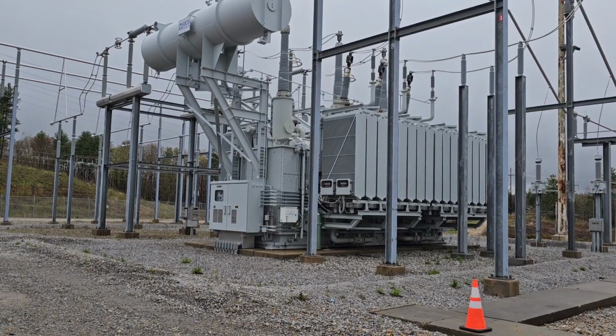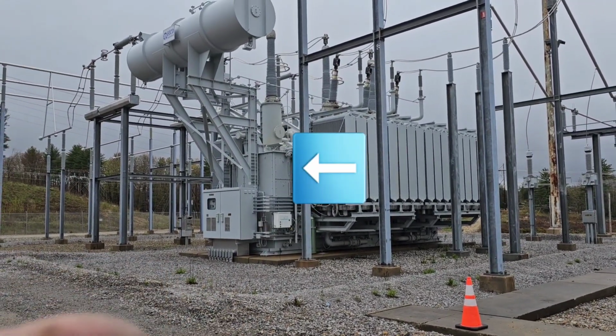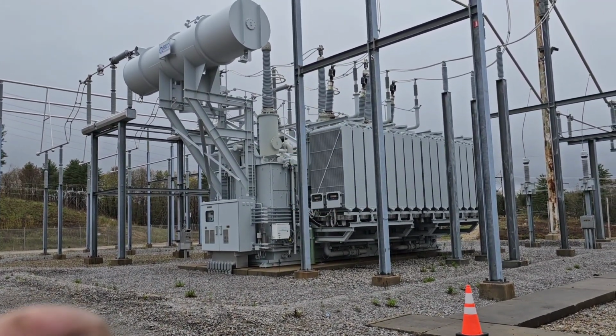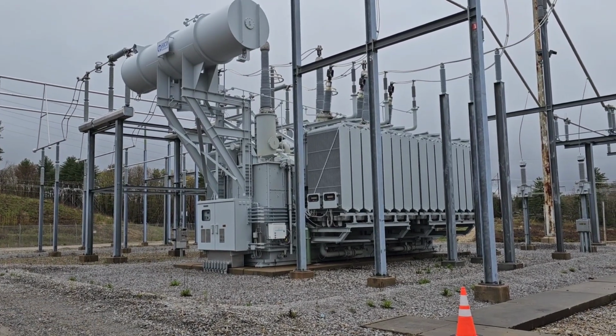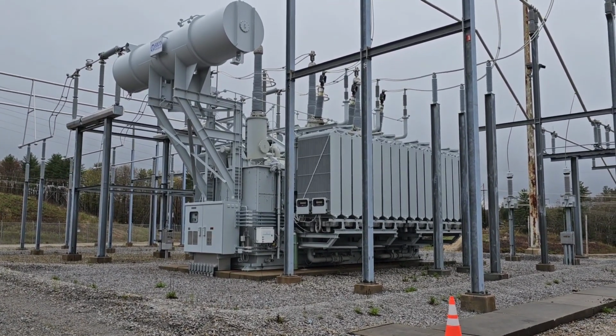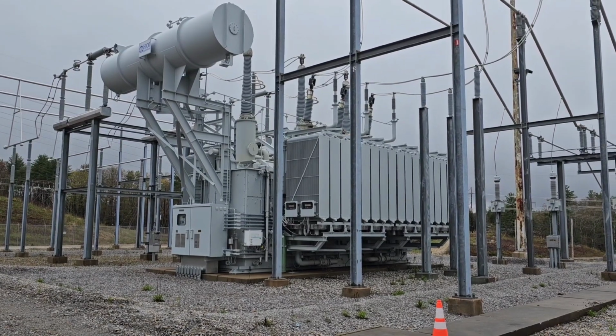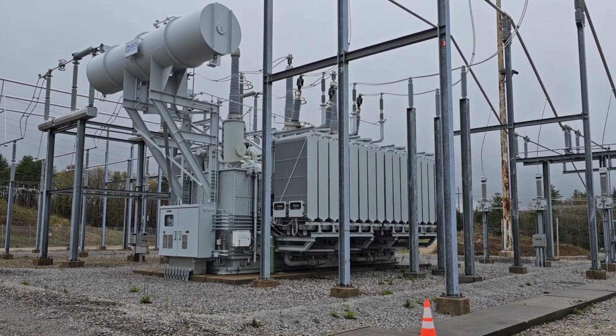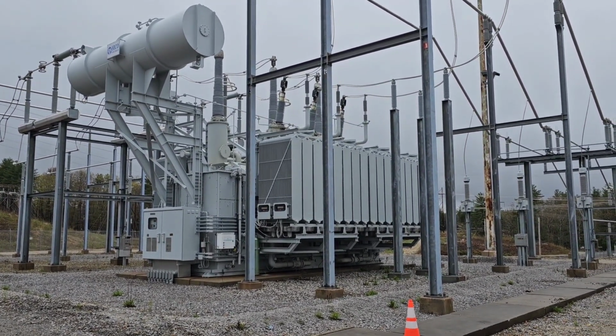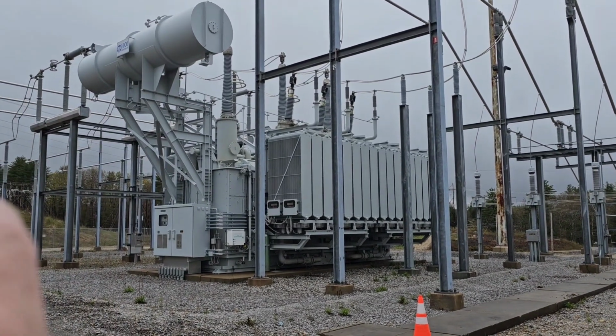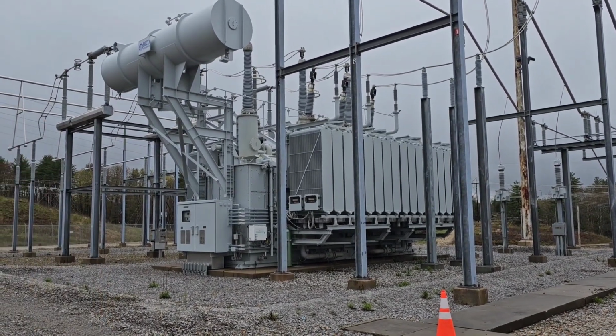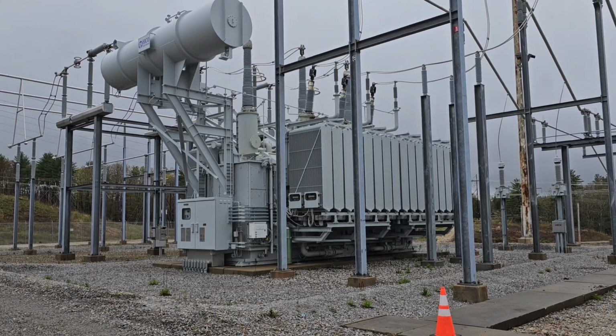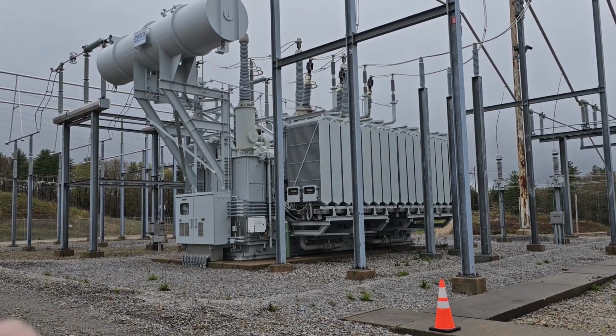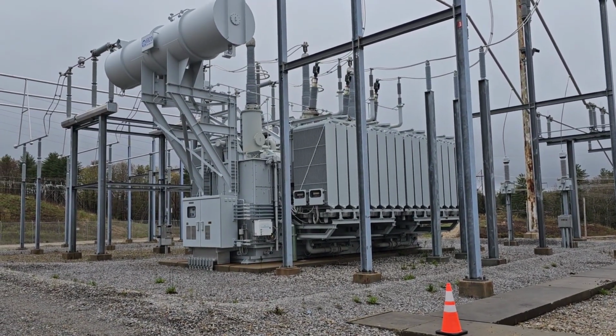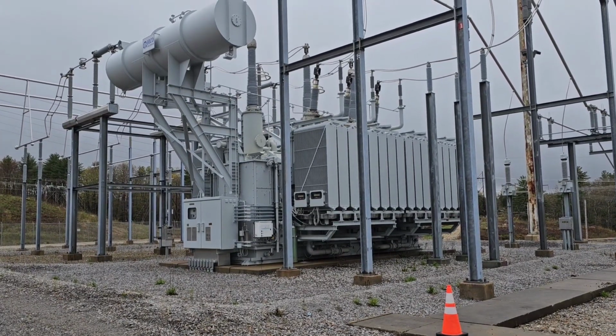This has what's called a load tap changer on it, so it can change the ratio slightly to adjust for power demand. We can get more into that later, but that's basically what this is and how it works. So if 100,000 volts goes in on the low side, 300,000 volts comes out on the high side. And if 300 amps goes in on the low side, 100 amps goes out on the high side.